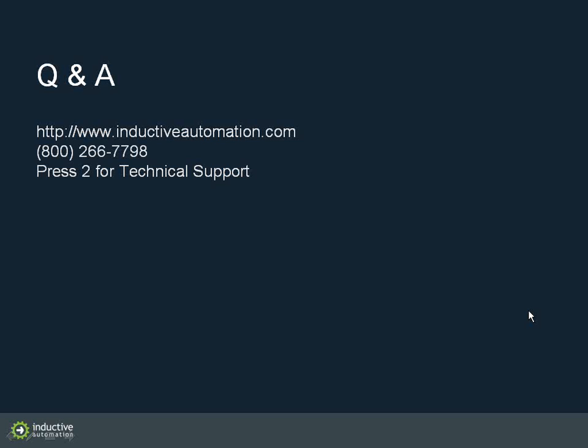Another question here from Brian. Does Ignition use the item's name or item's target field when creating columns, specifically the name of the column? And the answer to that is yes. It uses that target field. If the target field is set to database field, then it will use the name as the column name in your database table.